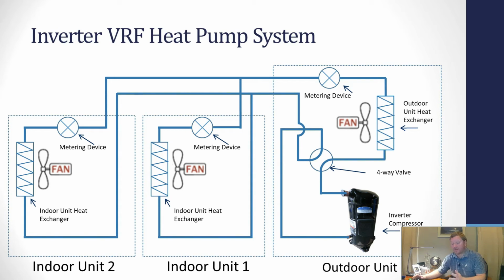And the way that I've kind of put everything together over the years is anytime you have 3 zones or more, VRF makes way more sense. And if you have 3 tons of capacity or more, VRF makes total sense. One of the biggest arguments, which we'll talk about at a later date, is cost. The VRF systems cost more, so I'm doing mini splits all the time because they're easier to sell. And I get it, but when you get to 3 indoor units or you get to the 3 tons of capacity, the cost difference is much closer than when it's like 1 zone or 2 zones.